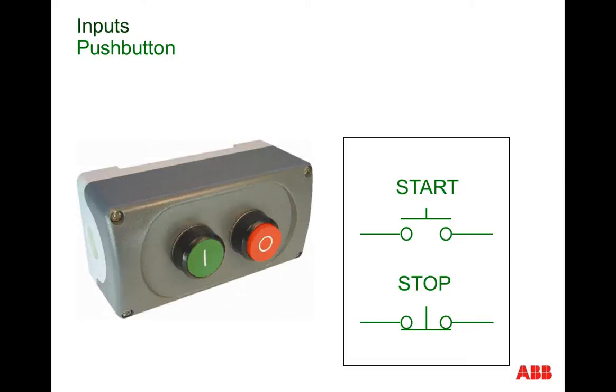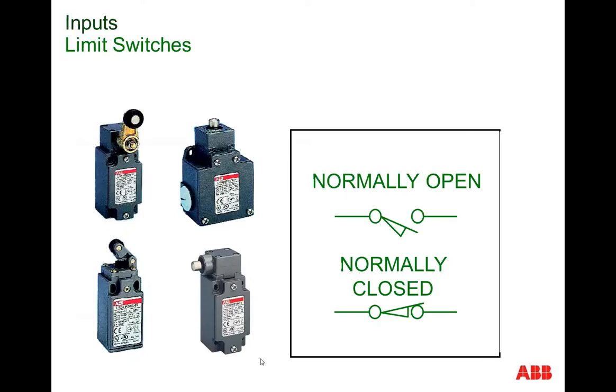Now, a very typical example of an input device would be a push button station as shown here. 1 meaning on, 0 or red meaning off. Notice that there is an air gap on this symbol for the start push button. This is designed to be a circuit symbol, and power is designed to be flowing from left to right through these wires or these lines that are shown on the symbol. You press the start button down, you connect the circuit, and you start an electric motor or a circuit. Conversely, look at the stop button symbology, and you notice that it's a normally closed device. In other words, it's conducting current in its off state or its shelf state. If I press the button down, I will open up this circuit, hence I discontinue power flow through the device.